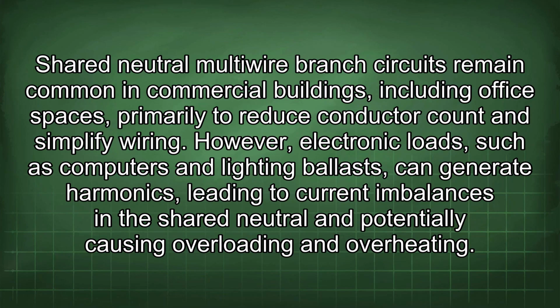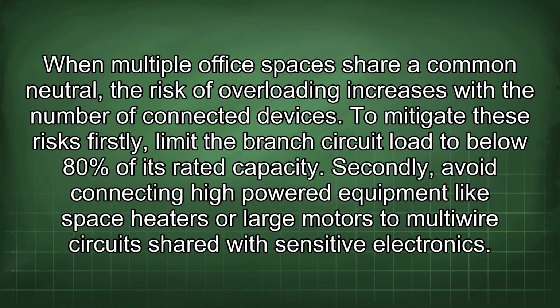Shared neutral multi-wire branch circuits remain common in commercial buildings, including office spaces, primarily to reduce conductor count and simplify wiring. However, electronic loads such as computers and lighting ballasts can generate harmonics, leading to current imbalances in the shared neutral and potentially causing overloading and overheating. When multiple office spaces share a common neutral, the risk of overloading increases with the number of connected devices.